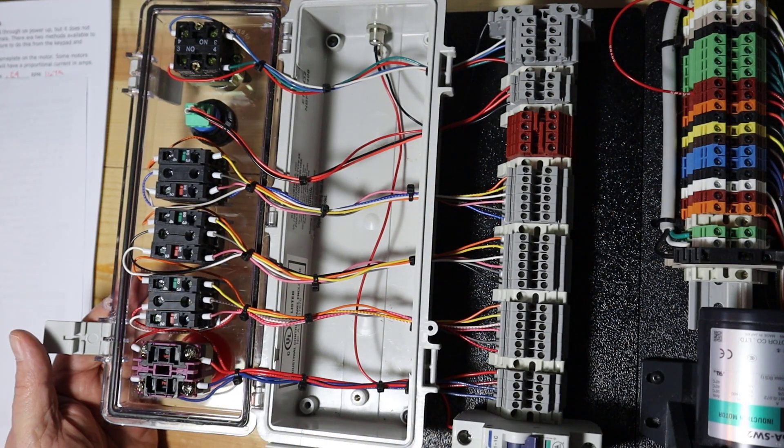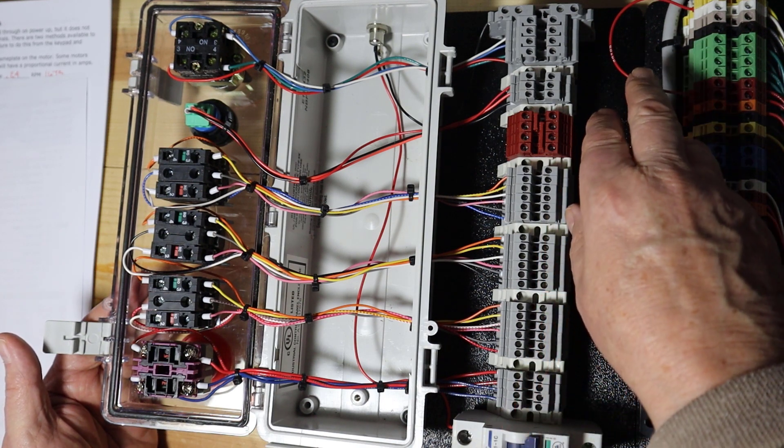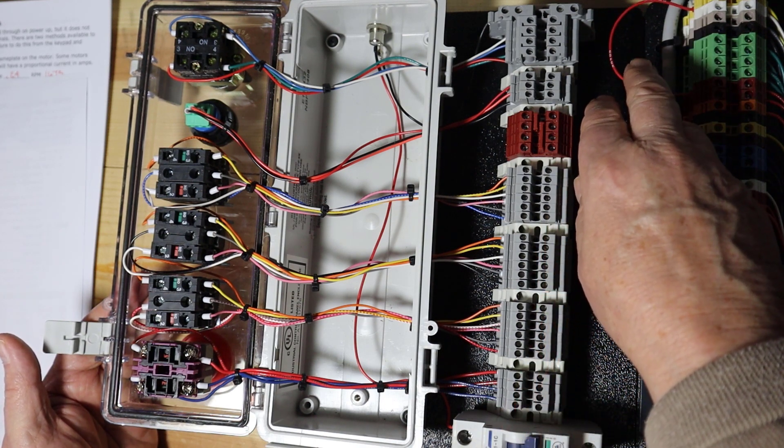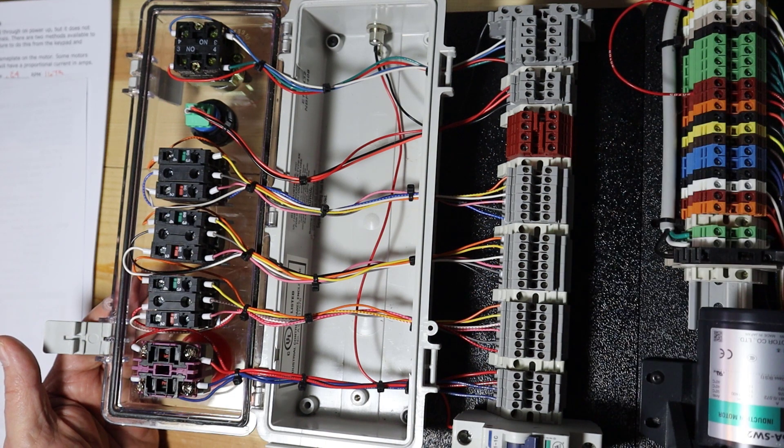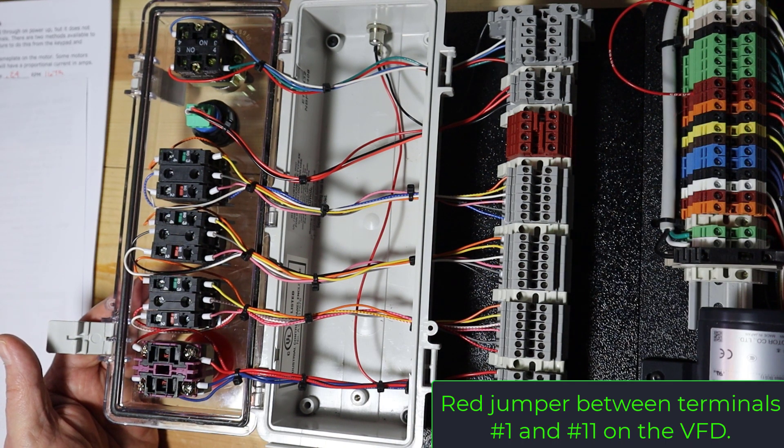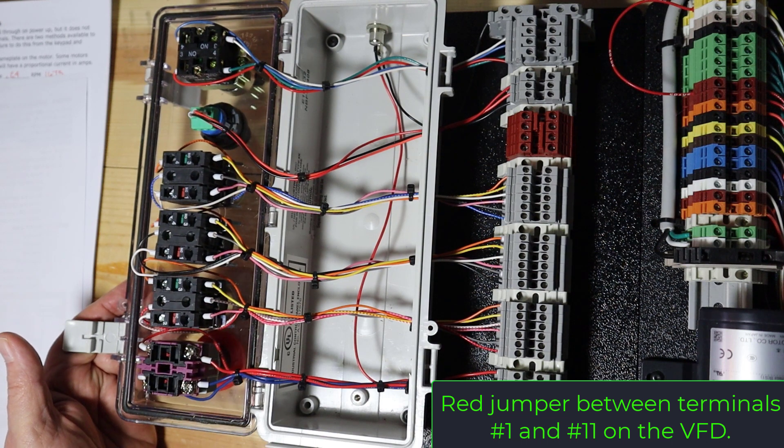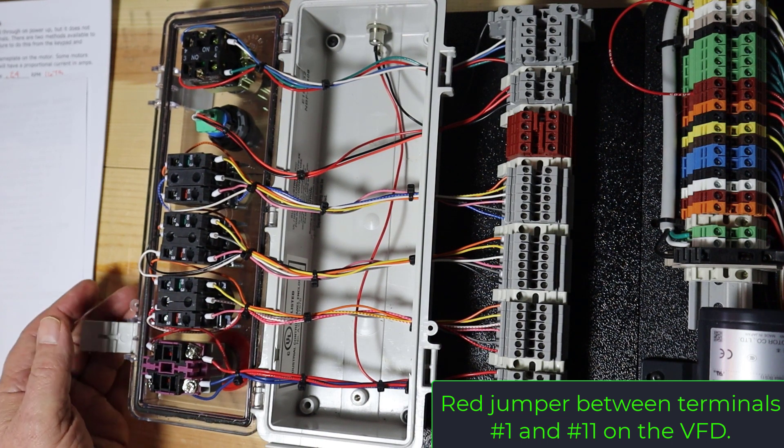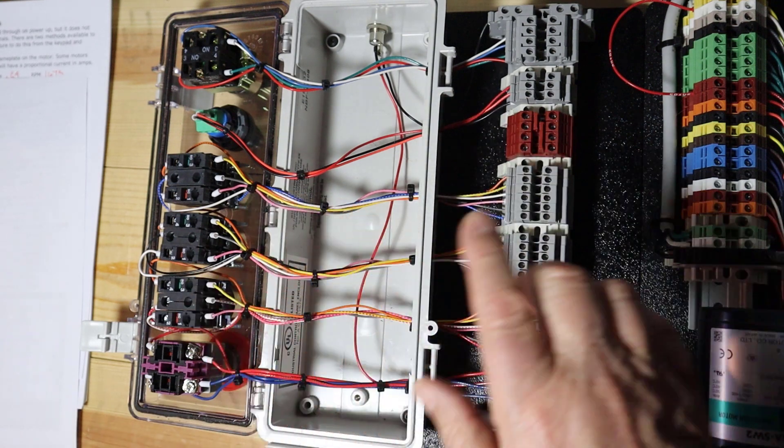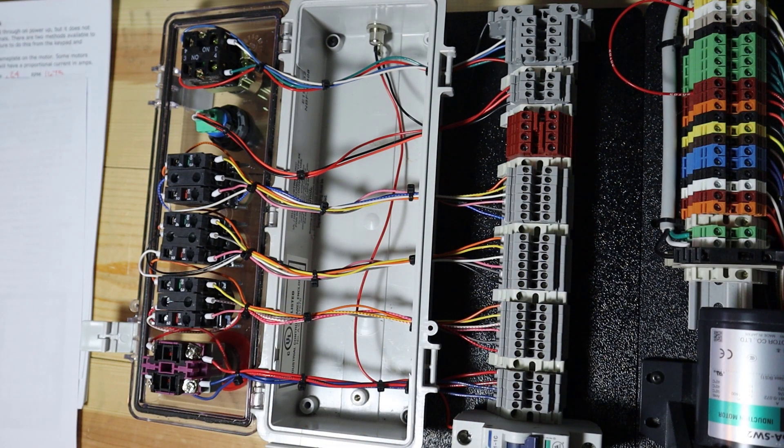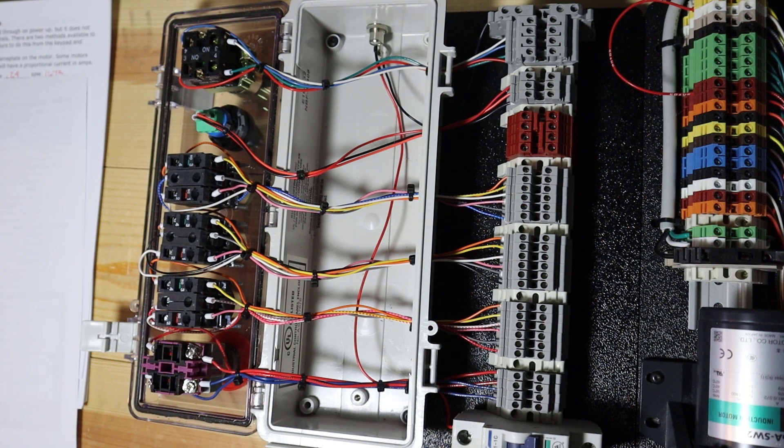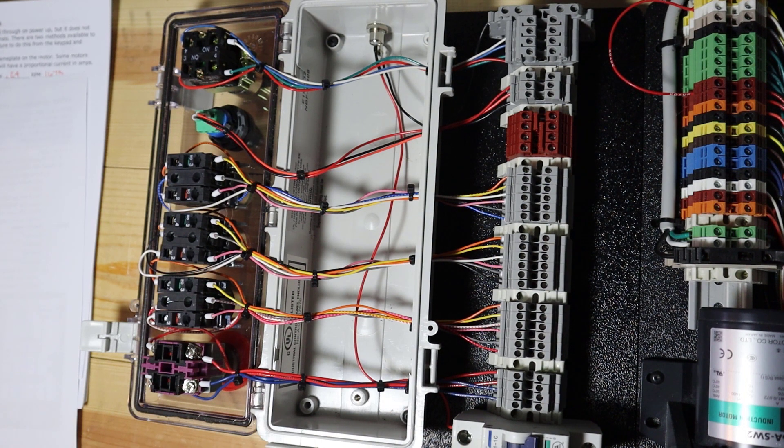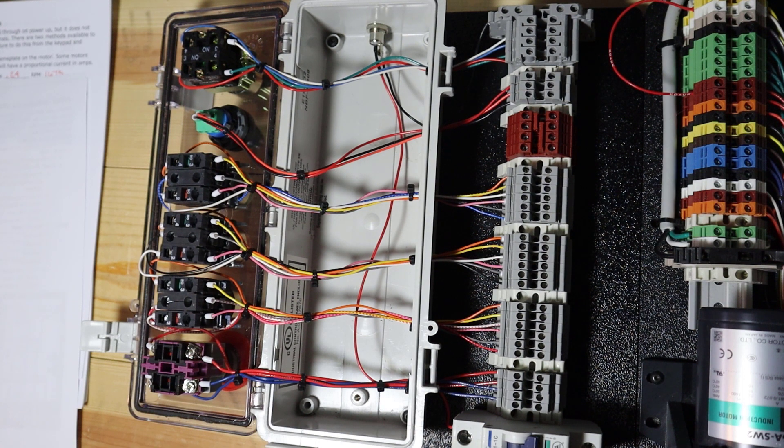So actually this connector here, that red wire goes down to the circuit breaker and then we can use a circuit breaker to power any of this as I/O. And what we're going to do, we're going to begin by taking this red wire right here. It's the jumper that comes from the factory that allows you to run it in the default mode and we're going to remove it and add some of these devices into that circuit.